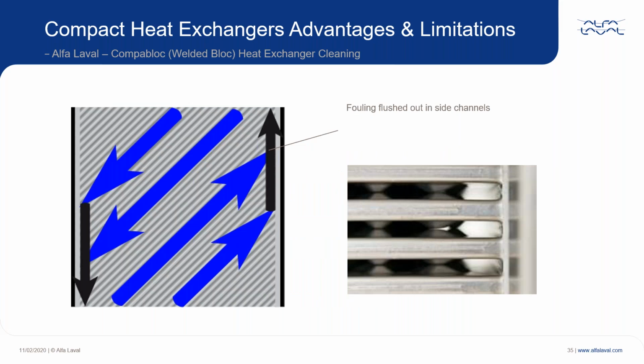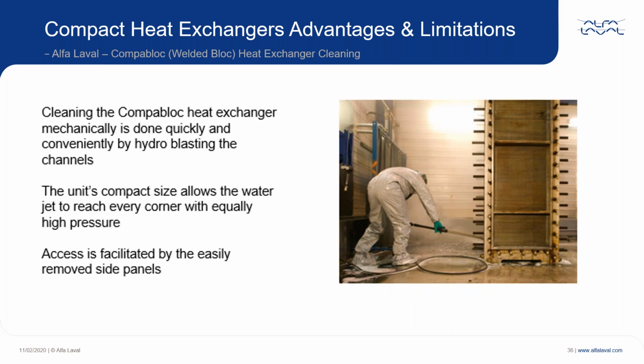And the beauty of the Compabloc is when you do want to clean it, you can take it apart, take the panels off the side, and it's 100% cleanable. If you throw a pressure washer through it along the edge, you've got channels where all the fouling will be flushed out, so all of the plate will be clean. Again, it's just a little picture showing someone who's taken one offline and given it a good clean.